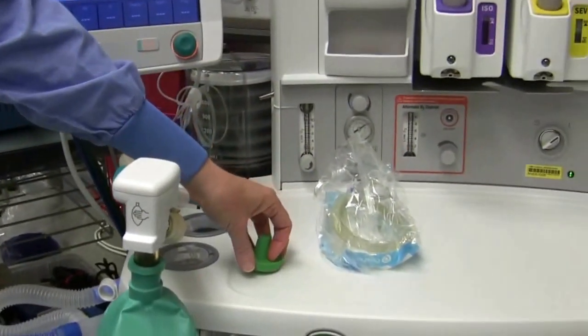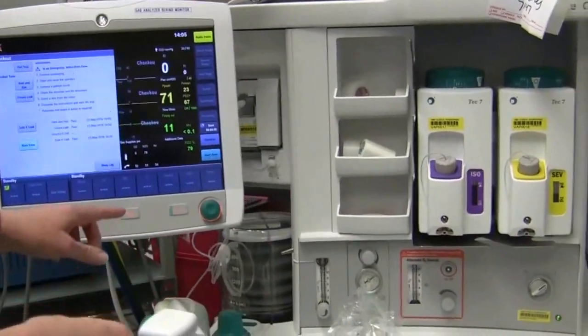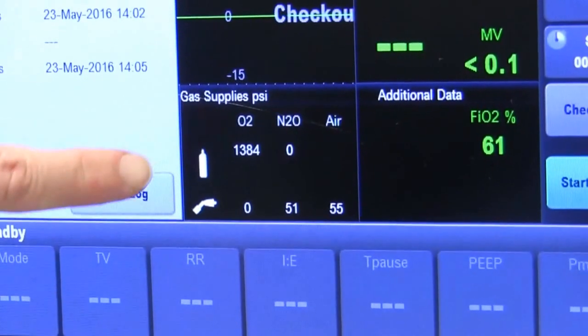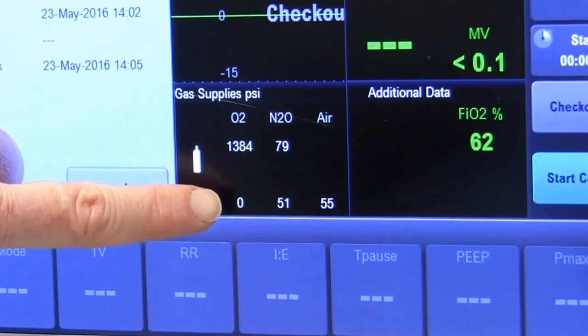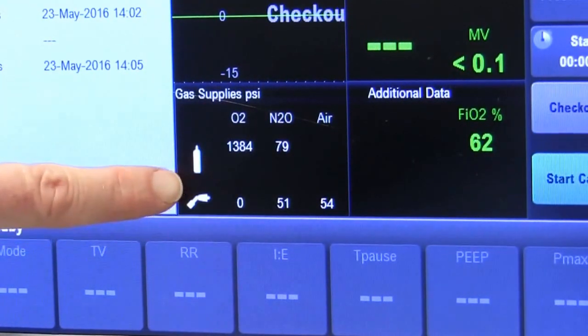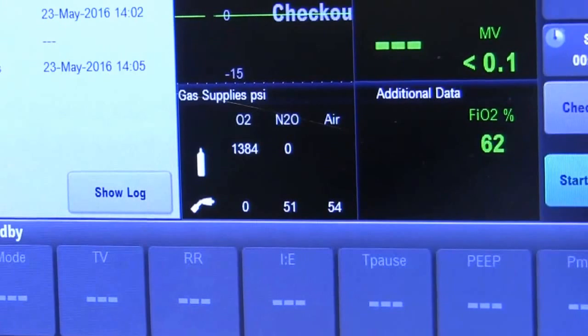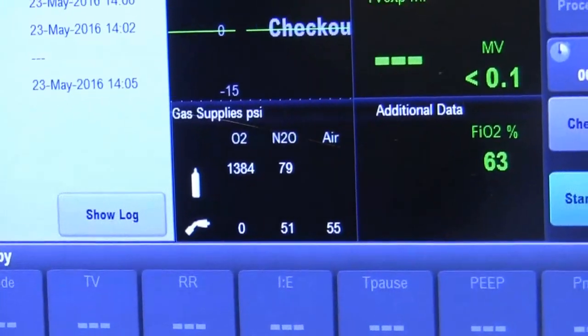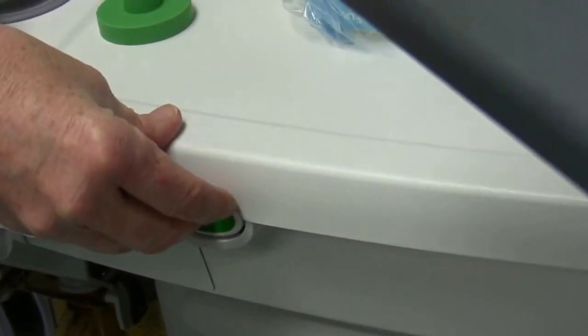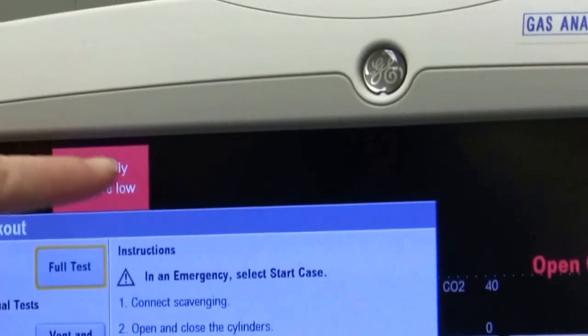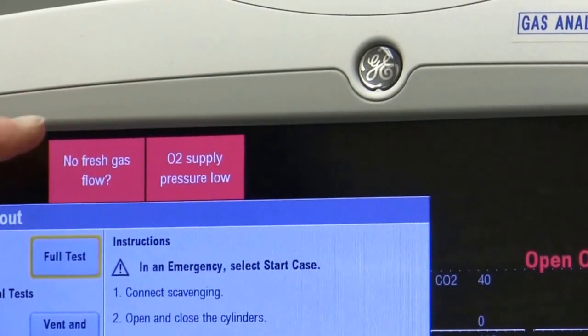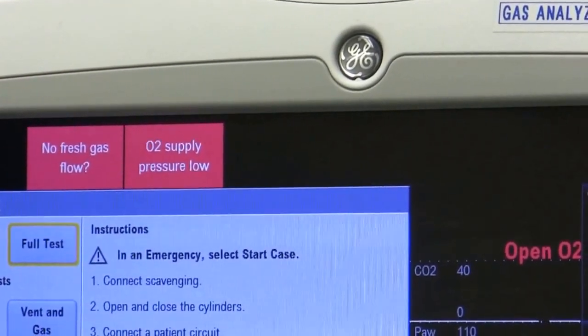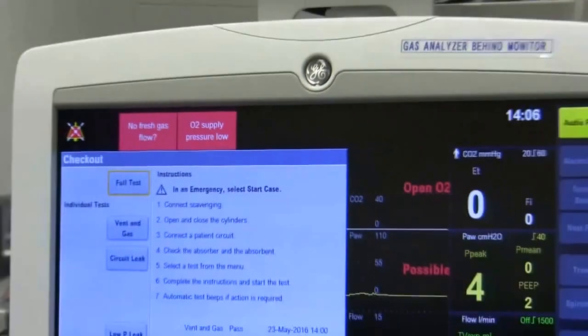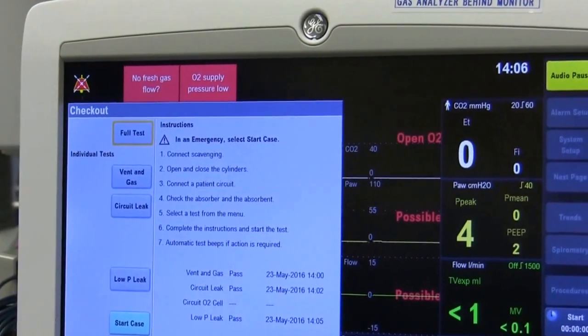I go behind and I check my oxygen. So this square right here is showing you we have 1384 in the tank, and right now we have 0 in the main line because I've disconnected it. I'm now going to flush by hitting the flush button because I want to see the alarm say we're out of oxygen, and that will come up here in red. It will beep if you have a case going on. Otherwise, right now it just comes on in red. I'm going to reconnect my oxygen source.